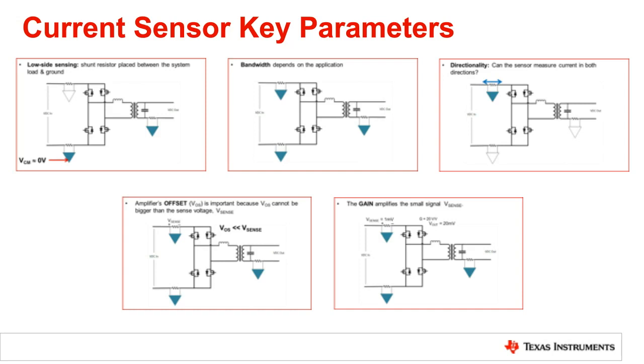Whenever we look at bandwidth, the difference at different points inside the system is whether we're measuring instantaneous or average current. On the actual control side, we're looking at instantaneous current, which the DSP needs for the control loops, so we want a fairly high bandwidth here, usually in the 200 kilohertz or more range. Whenever we're doing average current, the bandwidth can be a lot lower - this would be the input to the system if we're just doing bulk energy measurement, or the actual output to the vehicle, where we don't need as fast a response time.